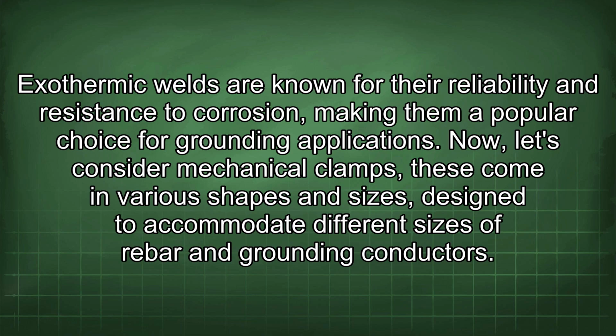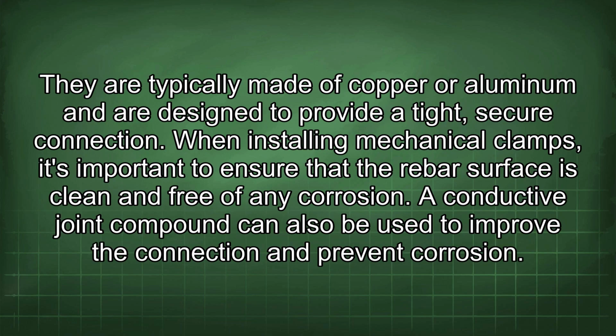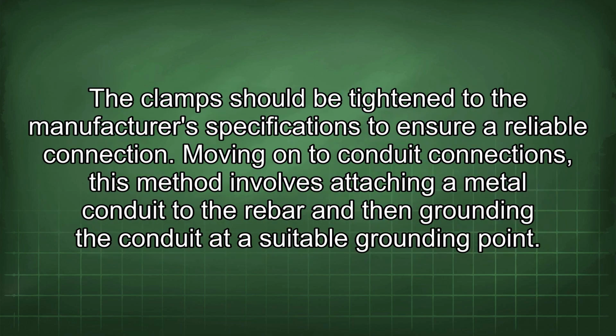Now let's consider mechanical clamps. These come in various shapes and sizes, designed to accommodate different sizes of rebar and grounding conductors. They are typically made of copper or aluminum and are designed to provide a tight, secure connection. When installing mechanical clamps, it's important to ensure that the rebar surface is clean and free of any corrosion. A conductive joint compound can also be used to improve the connection and prevent corrosion. The clamp should be tightened to the manufacturer's specifications to ensure a reliable connection.